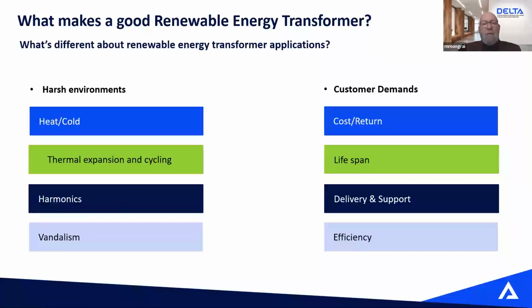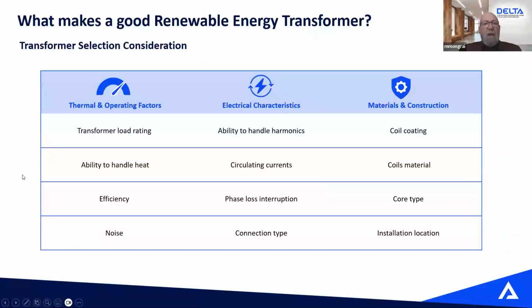So again, we've talked about some of the differences between a renewable energy transformer and a standard transformer. When installed outdoors in the winter, you're exposed to lots of cold, snow and blowing snow. In the summer, you're exposed to lots of heat, if you have a rooftop installation, for instance. You might be subject to vandalism if your system is not installed in a protected area. Harmonics: as soon as you have an inverter, there are going to be harmonics involved in the system. Thermal expansion and cycling, we've talked about that. Your customers are looking for a proper lifetime, a very efficient transformer, and good support to determine the best transformer for your system. There are many criteria we need to look at when we put a transformer in a renewable energy system, so all of that needs to be well taken care of.